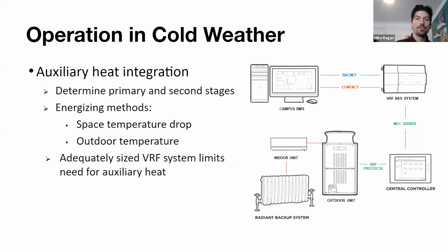Now, another way that we prepare for operation in cold weather is tying in with an auxiliary heat system. This could be a radiant system or electric resistance heat. If you have district heating, where you have hot water serving an entire campus, we could absolutely stage that as well. The way that we approach this is that we first want to determine the primary and second stages. The reality is we want our VRF, our heat pump equipment, to be the primary stage. It is a high efficiency system. You're spending the money for that high efficiency system. It should be operating as its primary stage. And the second stage should be picking up where the VRF system may fall short, or you may programmatically change it in such a way that the second stage would kick in at certain temperatures.